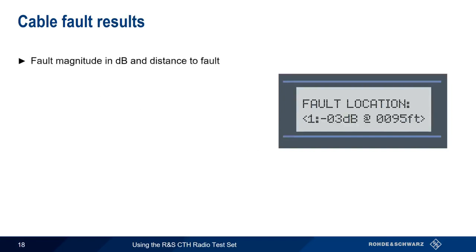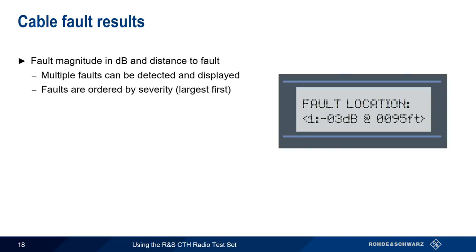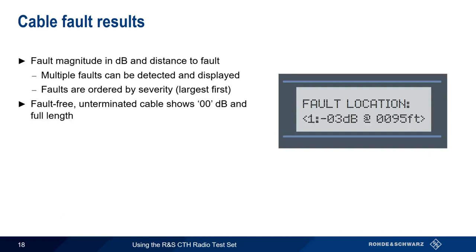The CTH provides both the magnitude of the fault in dB, as well as the distance of the fault for one or more faults. Multiple faults are numbered sequentially, ordered by severity — the first fault is the one with the strongest reflection. Note that a low-loss open or unconnected cable will reflect almost the full signal power at the open end, and in this case the measurement will display 00 dB and the full cable length.